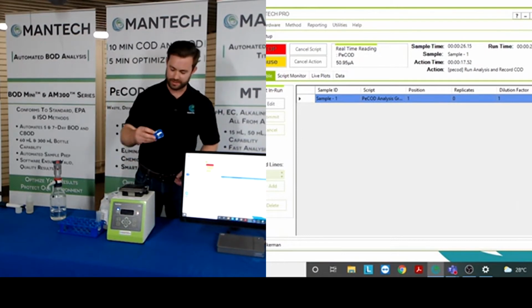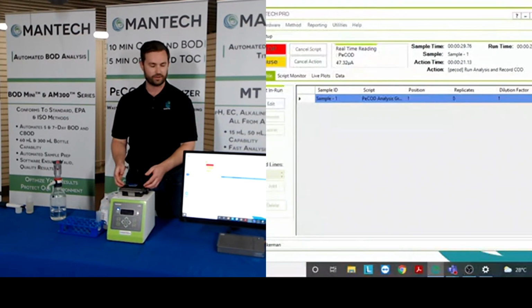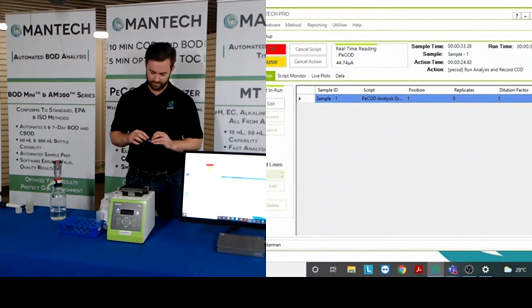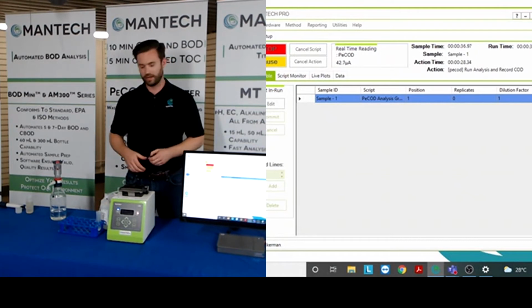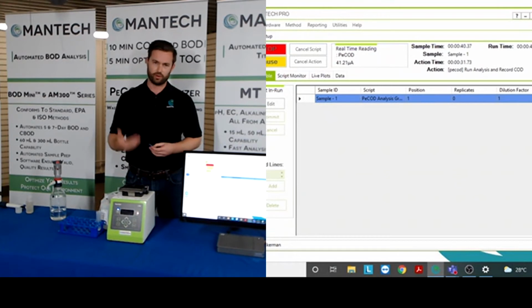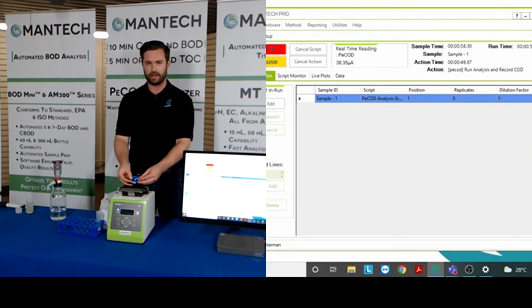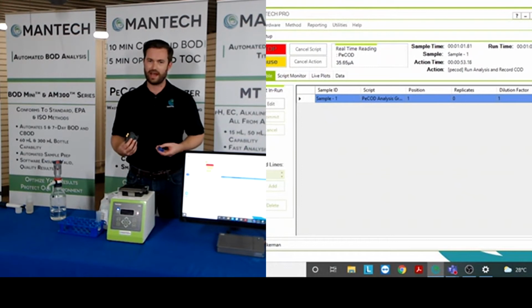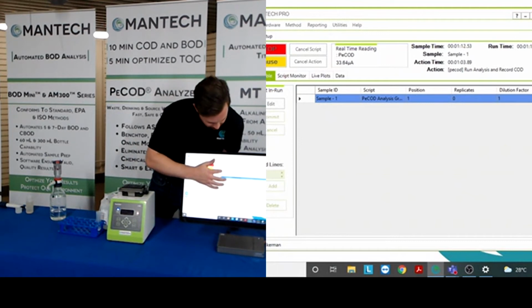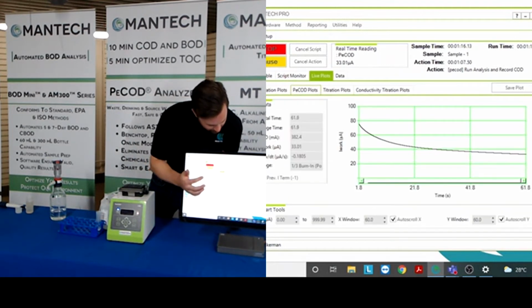So there's one of these little chips sitting up here in the top of the unit in the analyzer head, and that's got titanium dioxide in a very small cell right there. So the sample's introduced, and a blank is actually introduced first. So the same thing happens to a blank and then to a sample. It's rapidly oxidized by a UV light shining down into that small cell in the presence of titanium dioxide, and that produces a charge. And that charge is then captured by this piece right here. So both of these pieces are sitting in here inside the analyzer head. And this is an electrode right here. So this is capturing all of the charge, the energy generated from that oxidation reaction. And all of that is recorded. Over time, the oxidation proceeds. So if you're looking at the software right now, you'll be able to see exactly that.